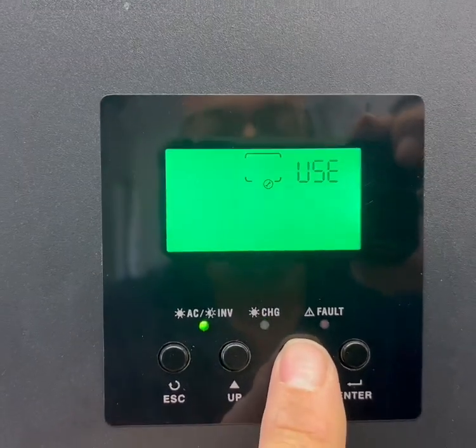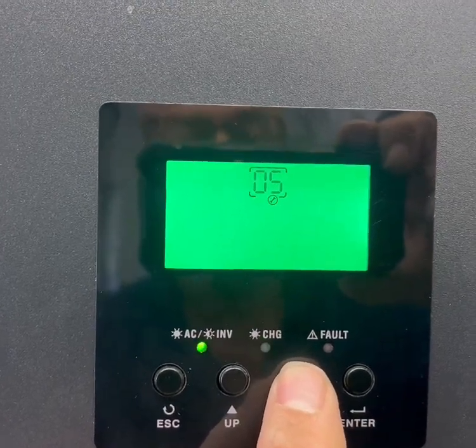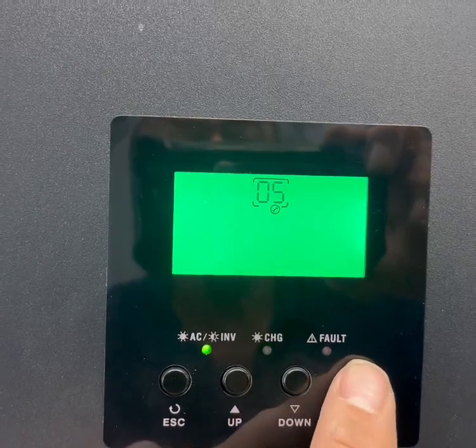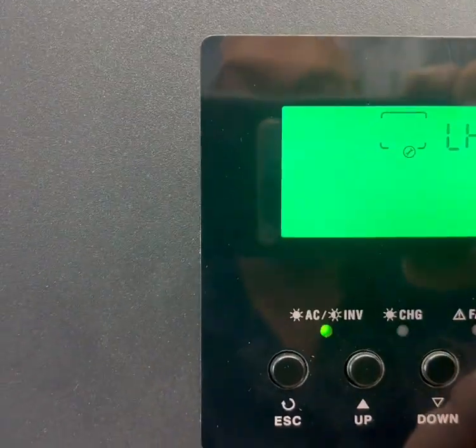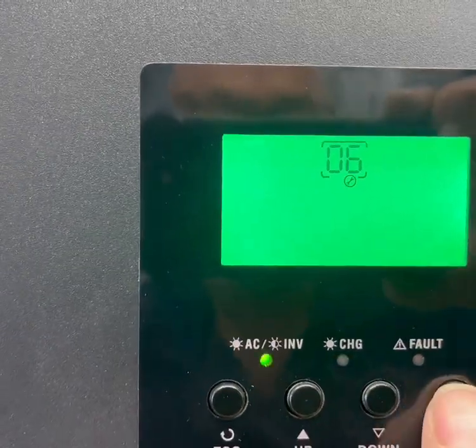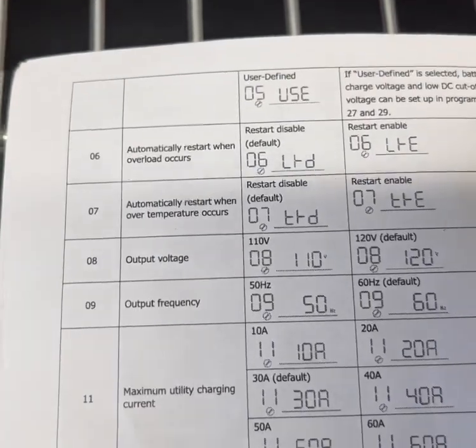Battery type number five — we had to set that at user defined because it's lithium iron phosphate. Your choices are AGM, flooded, or user defined, so if you're going to use a lithium iron phosphate on this MPP 5000 watt inverter, you have to use user defined. Number six is automatic restart, and we have that enabled. To change a setting you press enter and it flashes, then press up or down to change it, then hit enter again to confirm.